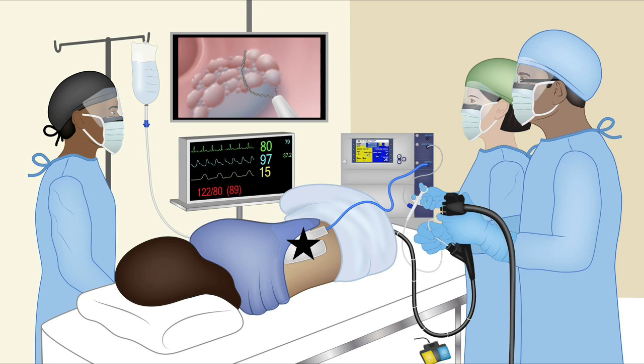The dispersive pad allows the current to be distributed back to the generator over a wider area, and having a good contact of the entire pad is critical. Otherwise, skin burns can happen. A faulty dispersive pad can create a big skin burn. So it's important to place it right.